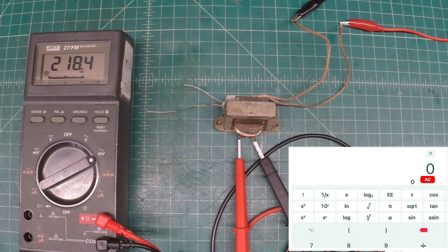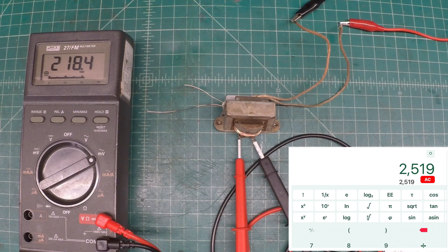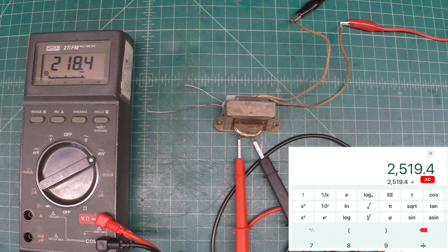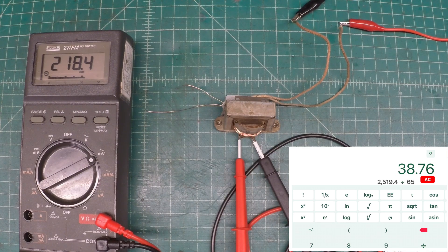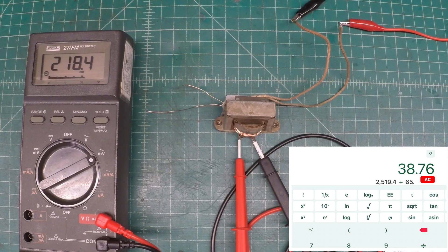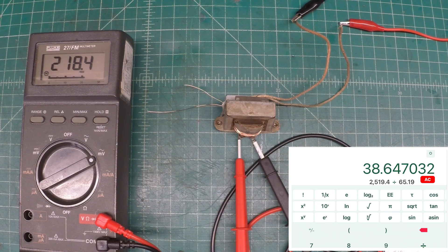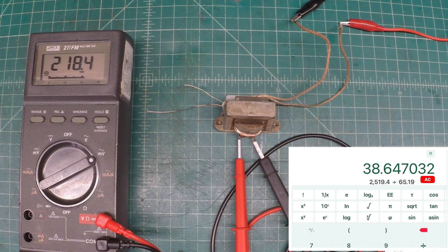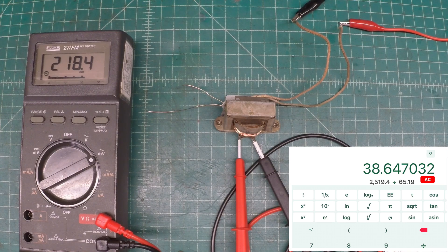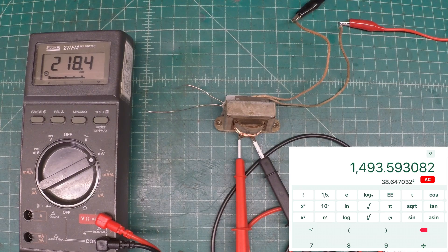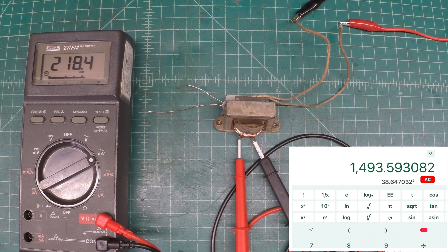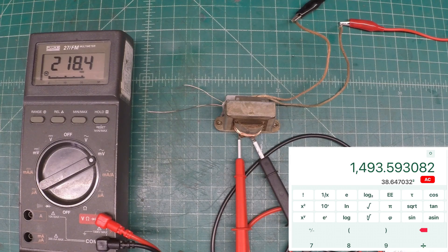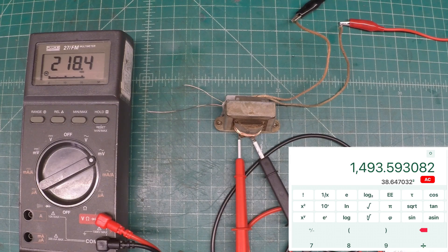Taking those numbers we can confirm that the turns ratio was correct. We can take the 2519 turns divided by the 65 and you can see we come back at 38.65 which matches our previous turns ratio for this particular transformer. We can then take the square of the 38 and some change and that gives us an impedance ratio of 1493 and a half which is also a match.